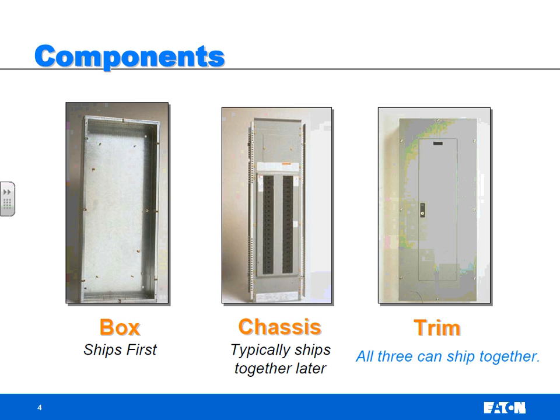A panel board itself comes in 3 parts. We've got a box, which is just sheet steel. So this is sheet steel that you hang on the wall. You've got a chassis, which is the bus. You've got a main breaker or main lugs on it, the feeder breakers in there, your vertical bus, and this whole chassis is built all as one assembly. So when this comes to the field, you take the chassis, mount it into the box, and then on the outside is what they call a trim.